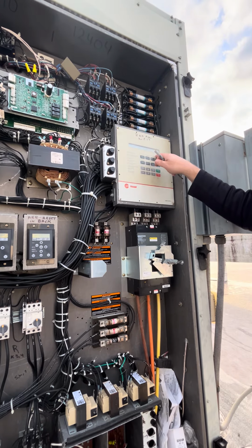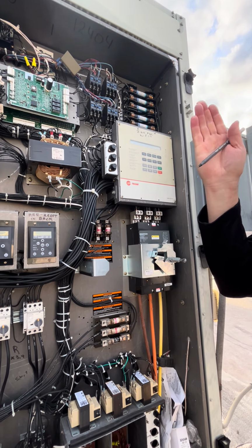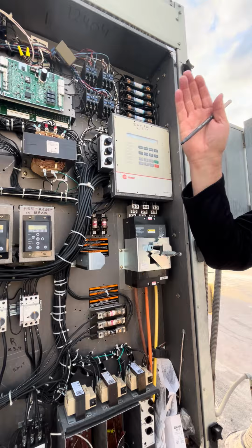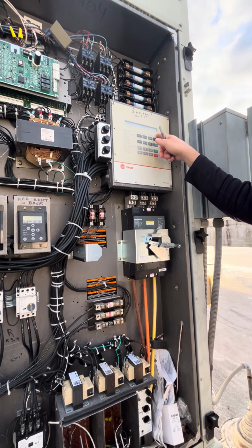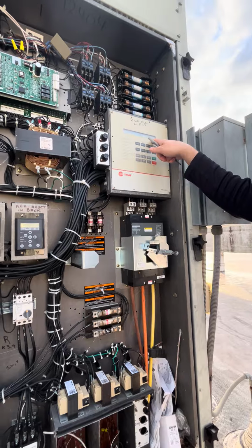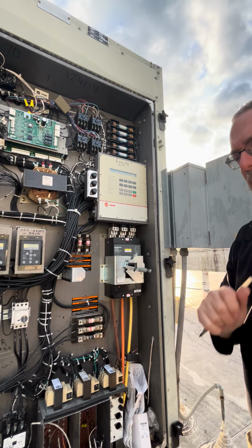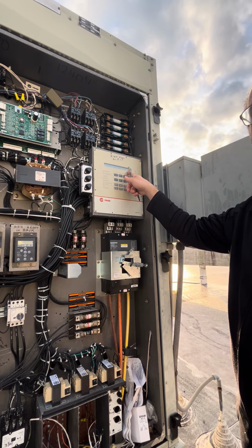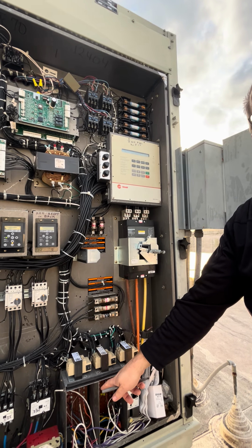The unit sees 6.72 volts. Remember, we're 0 to 10, 40 to 90. But we're going to give it 75. Right. So we're giving it 6.72 volts. The unit sees that as 75 degree air. Okay. All right. So we're at 72 degrees temperature downstairs. Our set point is saying 75. We've locked the cooling out through the demand limit contacts.